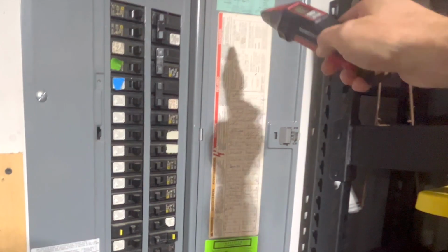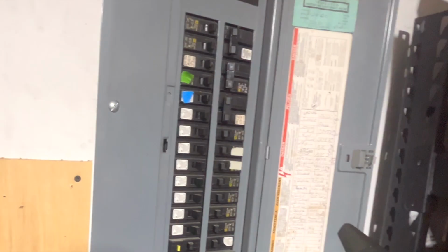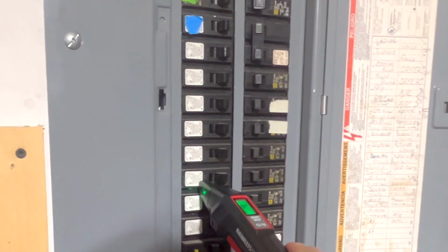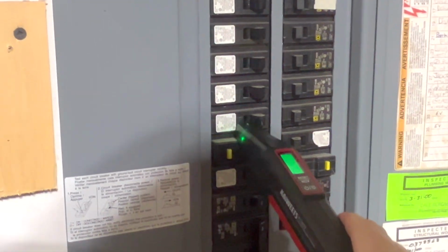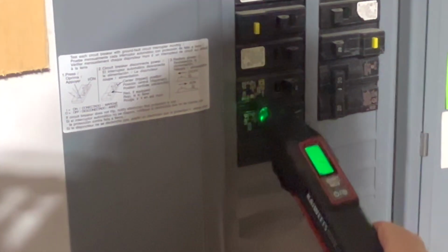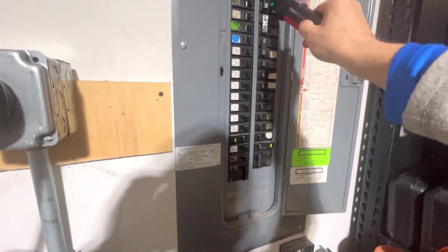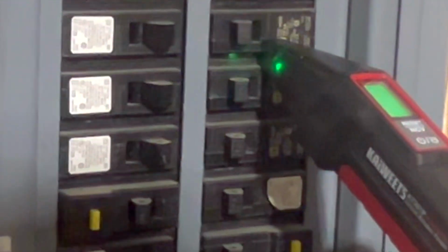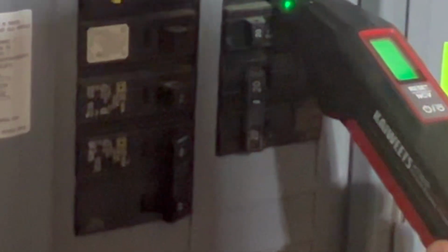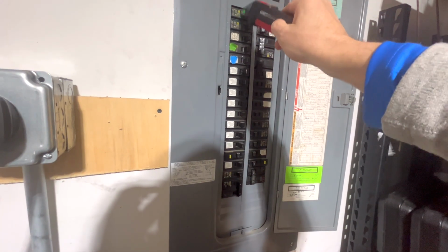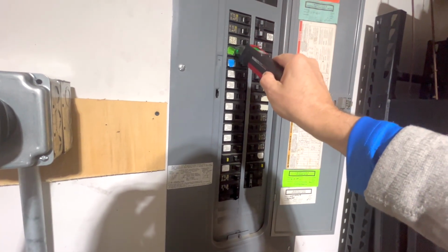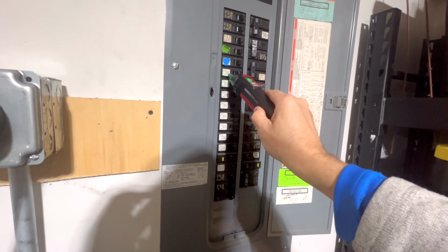This tool is especially handy when you don't have a list of all the circuits listed out. We're running this down the breakers one by one. Really not going to pay any attention to anything that beeps the first time around. It's just listening. So it's found a couple. Now do it again. This time we're going to pay attention to long beeps.